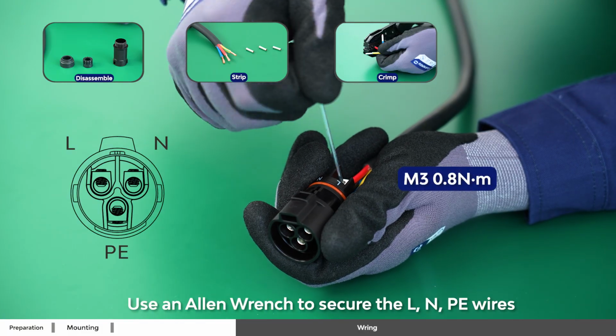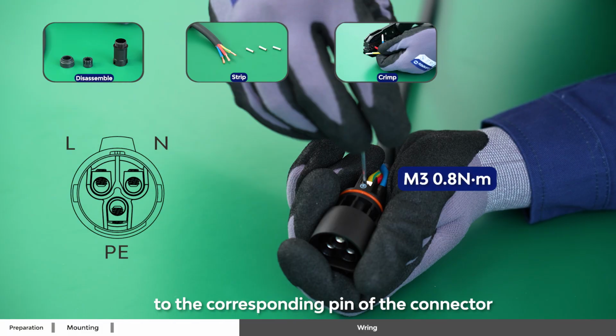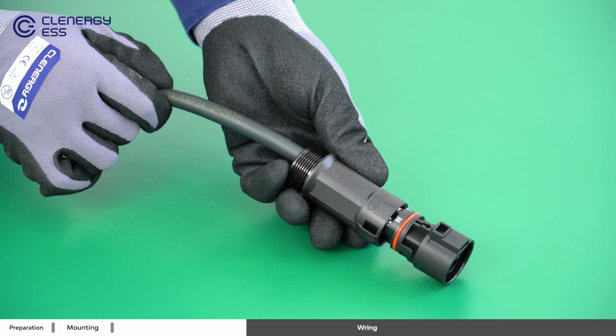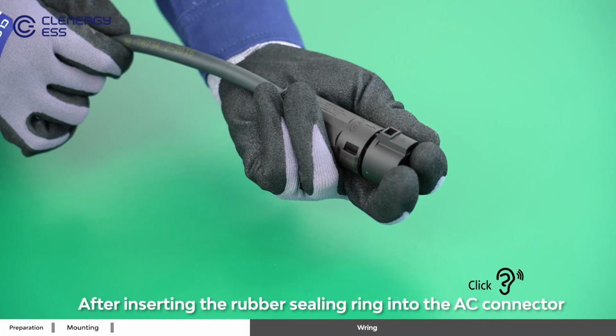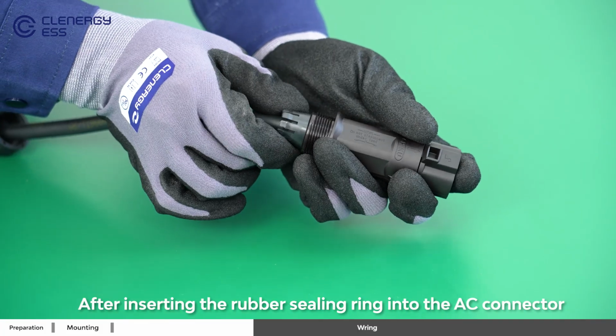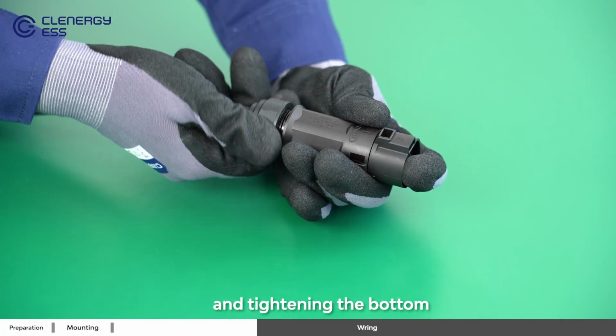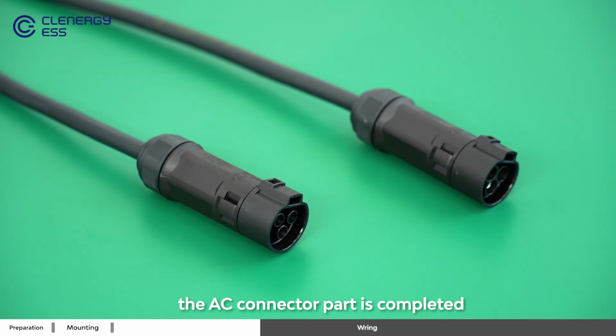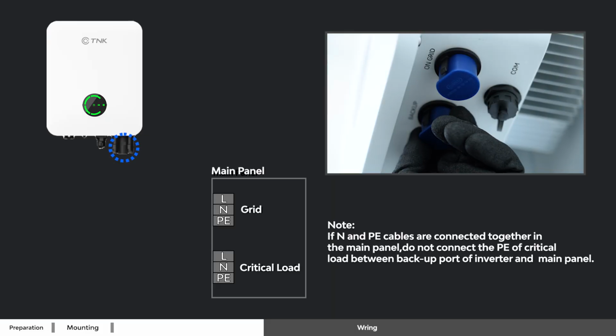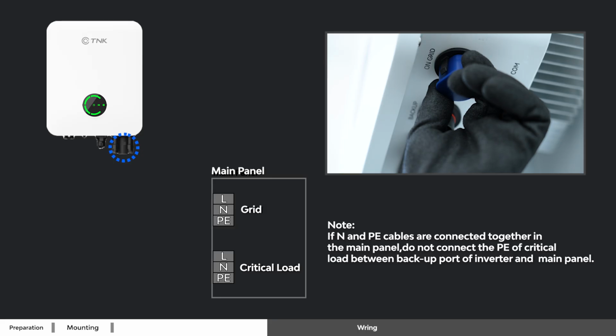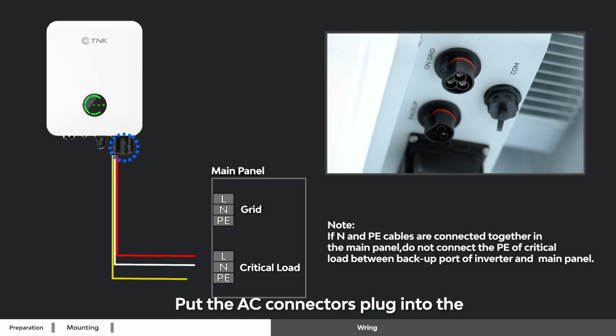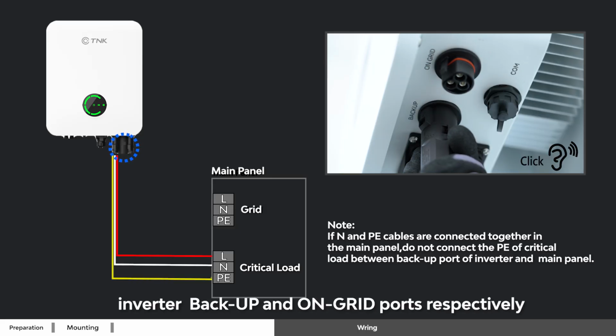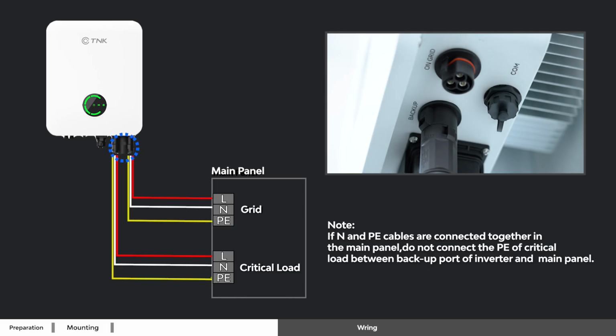Use an Allen wrench to secure the L, N, PE wires to the corresponding pin of the connector. After inserting the rubber sealing ring into the AC connector and tightening the bottom, the AC connector part is completed. Put the AC connectors plug into the inverter backup and on-grid ports respectively.